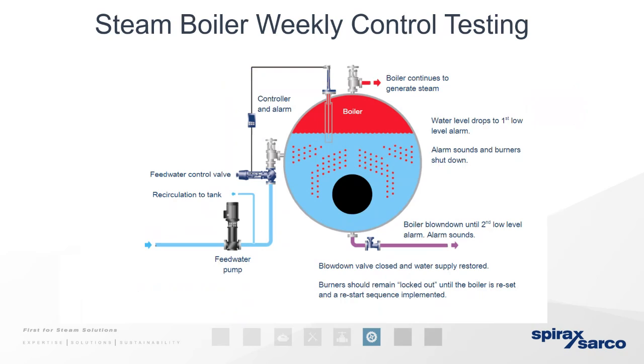So, weekly testing. This is undertaken by closing the feed water valve and then evaporating the water off until the level drops to the first alarm. We need to check that the alarm sounds and that the burner switches off. That's the important part on the first level, and it should be done weekly. So therefore, you're no longer producing steam. We then check the second low alarm is working correctly. We lower the water further by manual means until you reach the second alarm, which should sound the alarm and lock out the boiler altogether this time. That confirms our level alarms effectively.